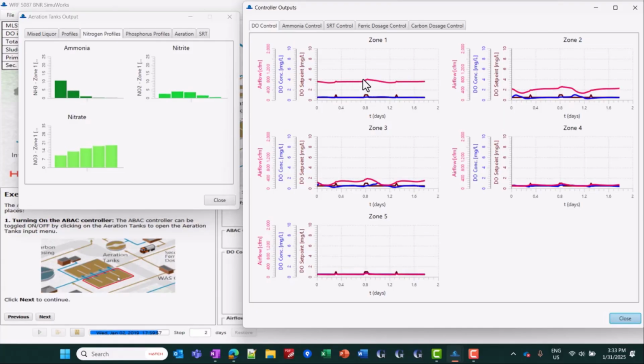We can see that the set point is bumped up here, and then there's an immediate increase in the airflow as it goes all the way down to the bottom. So that is a more sophisticated control, keeping the DO low when it's okay to do that, when the ammonia is in a good place. But when those heavier loadings come, it bumps up the set points accordingly.